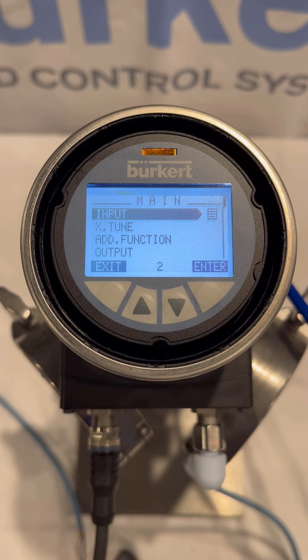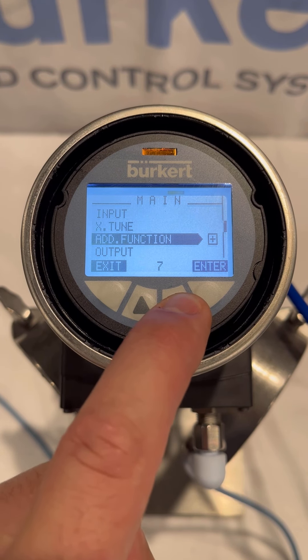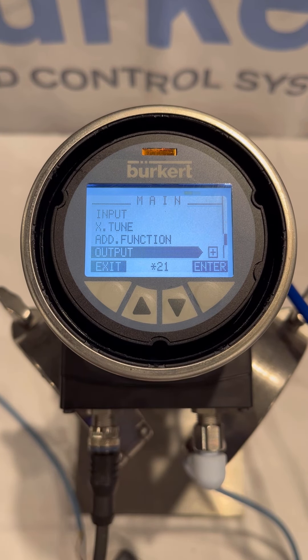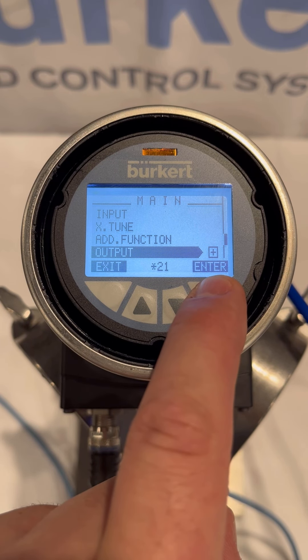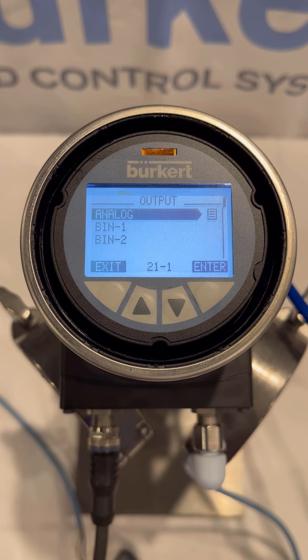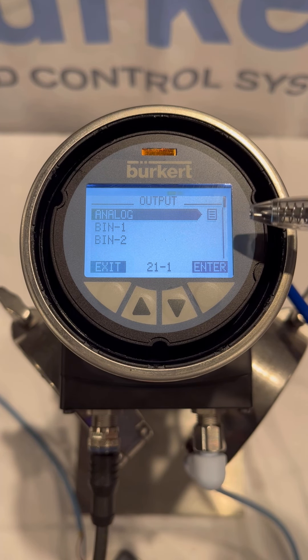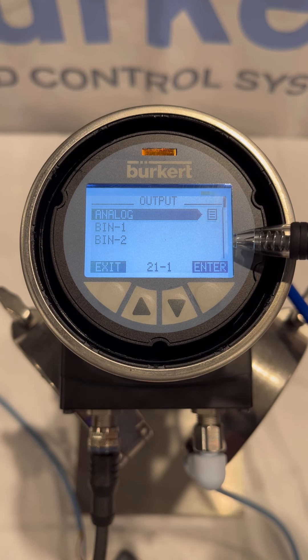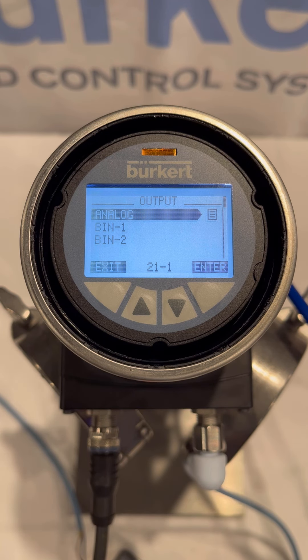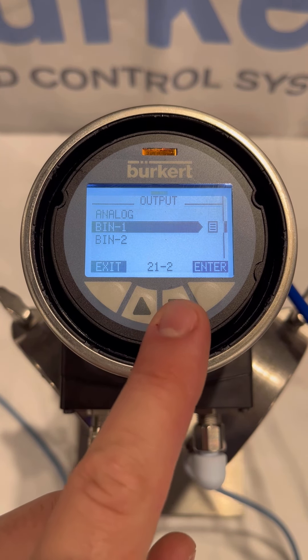We should now be able to view and access the output option. Scroll down to output and press enter. This positioner has three output options to choose from — one analog and two binary. Since we tied the blue LED lamp to binary 1, we'll select binary 1 and press enter.